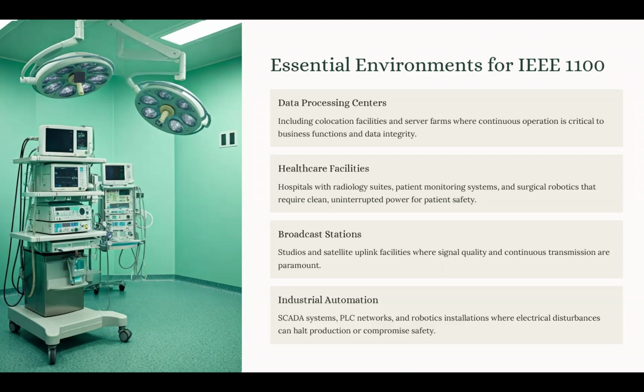The IEEE also recommends redundant power topologies, which is a secondary selective system with dual UPSs and backup generators, so they can maintain Tier 3 plus reliability. Isolating transformers are also recommended to suppress common mode noise from upstream feeders. And there are also some practices for harmonic control, which is using K-rated transformers and harmonic filters for servers with high nonlinear loads.